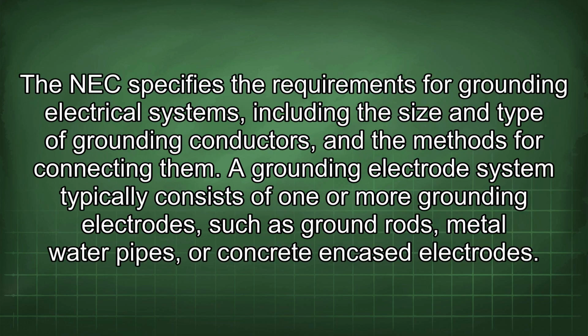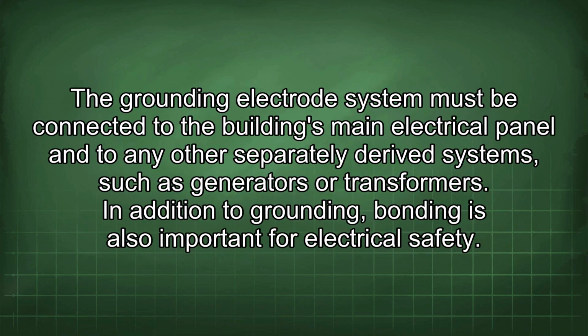The NEC specifies the requirements for grounding electrical systems, including the size and type of grounding conductors and the methods for connecting them. A grounding electrode system typically consists of one or more grounding electrodes, such as ground rods, metal water pipes, or concrete encased electrodes. The grounding electrode system must be connected to the building's main electrical panel and to any other separately derived systems, such as generators or transformers.